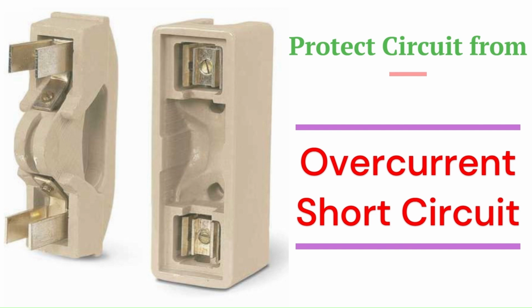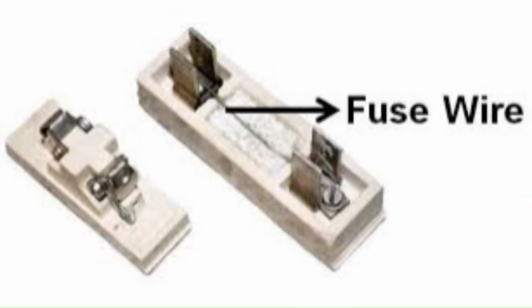While various types of fuses exist, their fundamental function remains the same. That is, to interrupt the flow of current when it exceeds a predetermined limit. In general, a fuse consists of a low resistance metallic wire enclosed in a non combustible material. It is installed in series with a circuit or device which needs to be protected from short circuit and overcurrent. Electrical appliances may be damaged in the absence of a fuse as they are unable to handle the excessive current according to their rating limits.